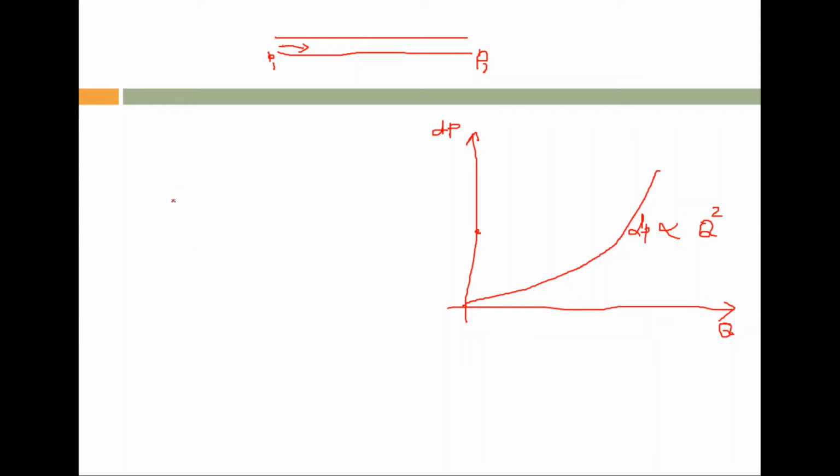If you have some bend, like some height difference like this one, then definitely, this one is the applied pressure P1, and this is the output pressure P2. Here you can see that this pressure difference has to overcome this static head. The liquid is filled inside this one also. We are transporting liquid from this point to this point, so this much liquid column will provide a head pressure also, static pressure.